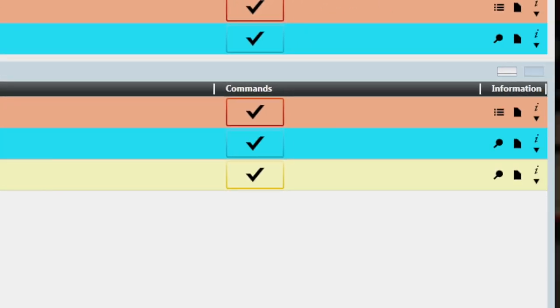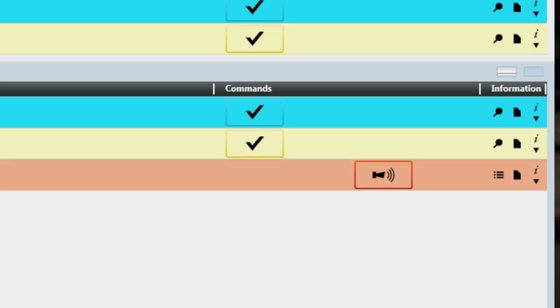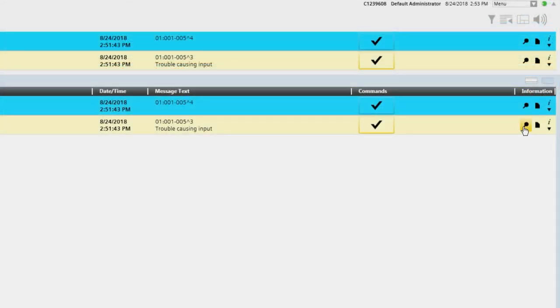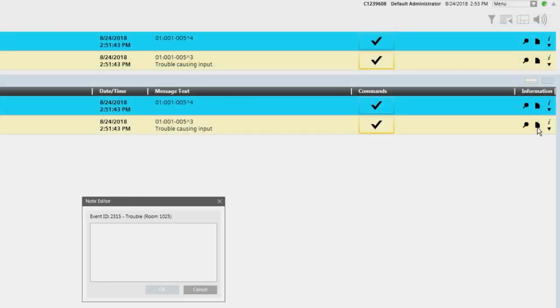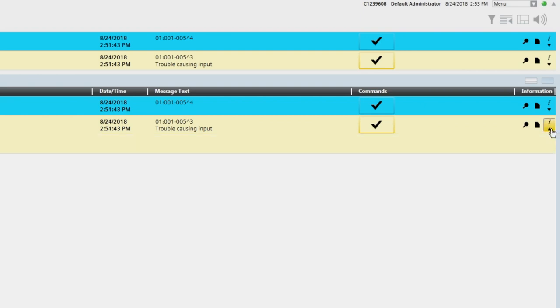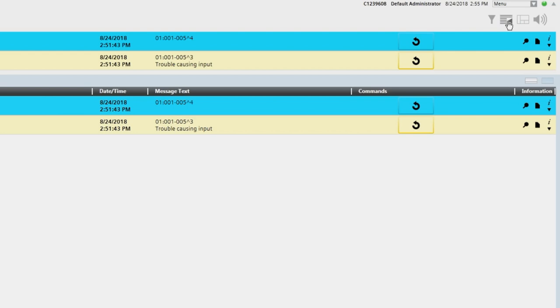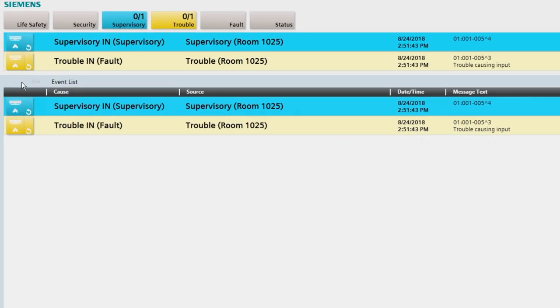The commands column contains the next available command to manage each event. The commands are acknowledge, silence or unsilence, and reset. The information column contains three buttons: open related treatment, log and event note, and show information text. Note that if the full event list is not visible and only the event bar is visible, click on one of the two display expand/collapse event list buttons. If there are more events than what can be displayed on a single screen, use the scroll bar on the right-hand side to view the additional events.